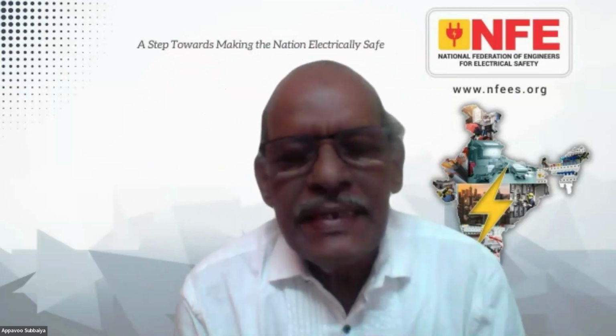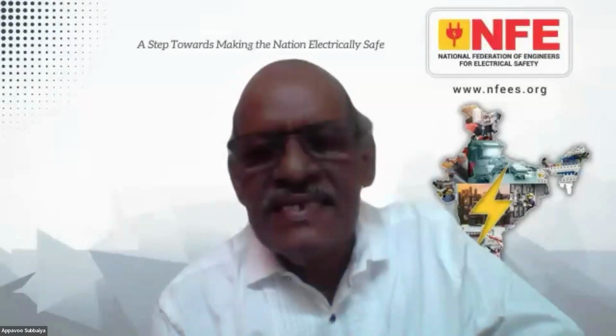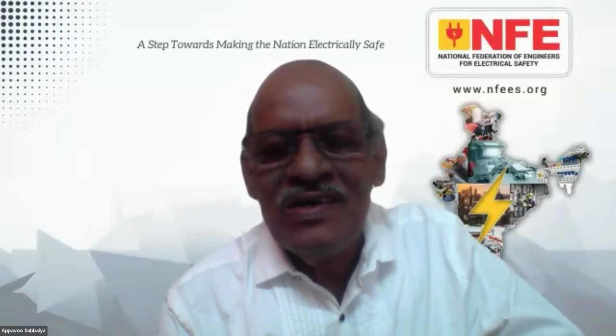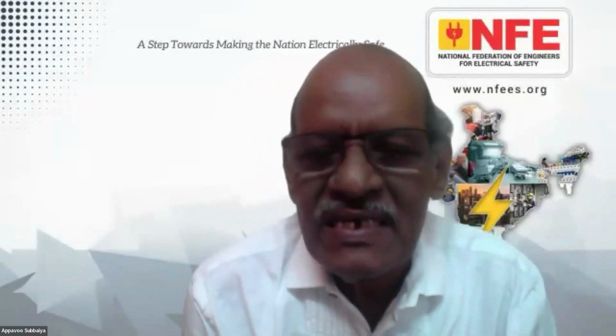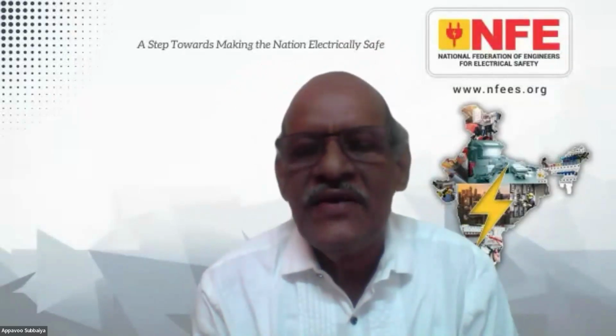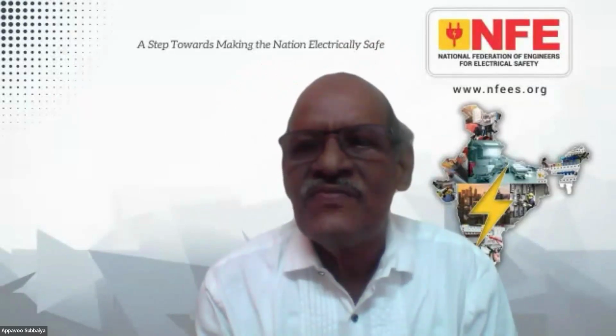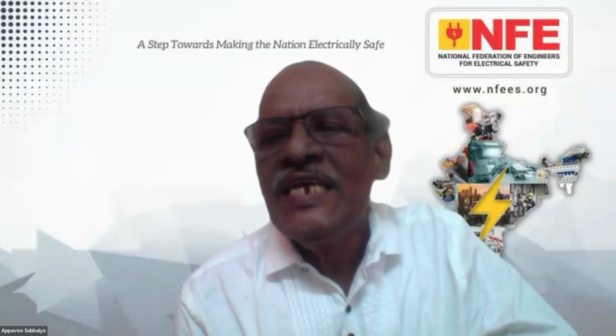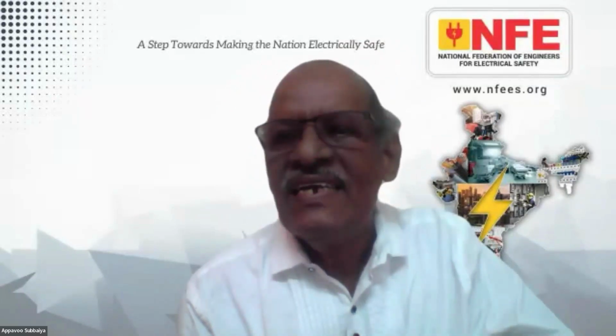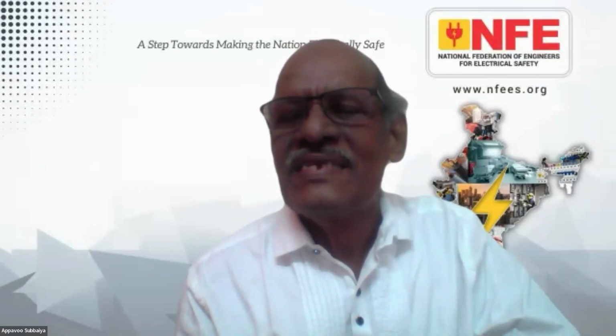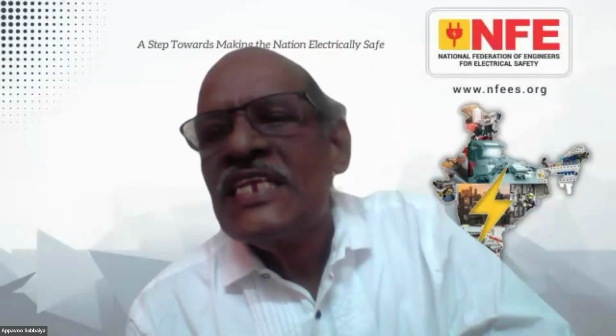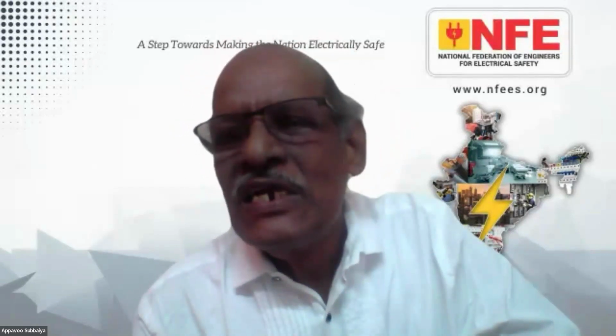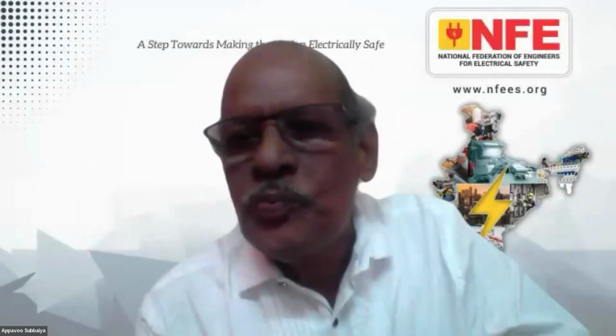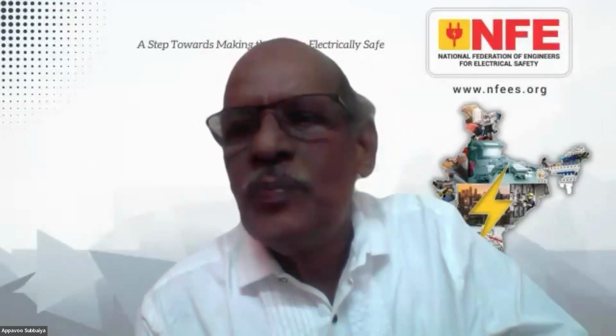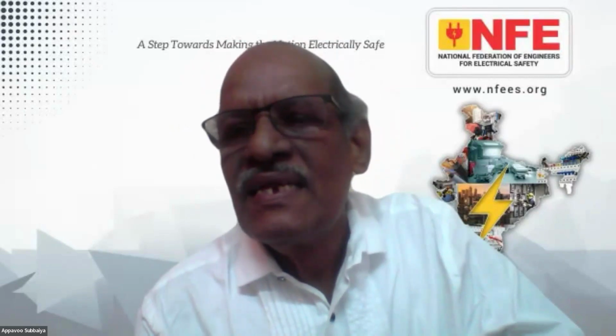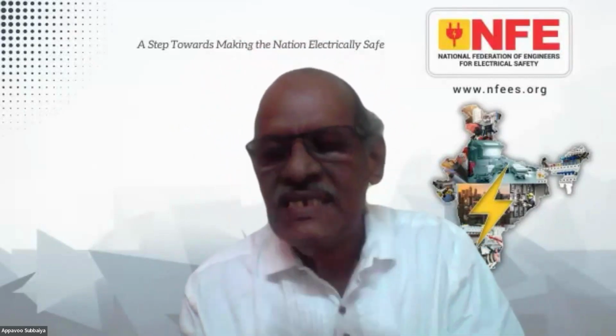We have already explained that the regulation has now changed from earth pit to earth loop. So because of our earlier preconceived, misconceived idea that earth pit provisioning everywhere will do away and actually provide extra safety is wrong. You need not provide any measurement for earth electrode - this has been taken away, previously it was there. It is available for the supplier alone. So the answer is there is no frequency for testing - you just have an earth electrode and it is for referencing only. You test the earth loop impedance, and this is for LV installation, applicable for the consumer LV installation. The supplier alone requires the earth pit electrode at the substation.